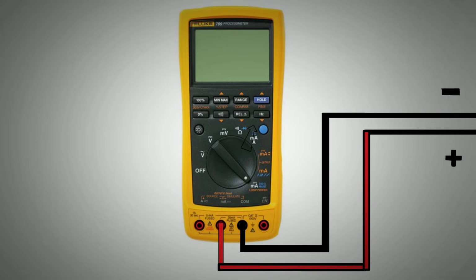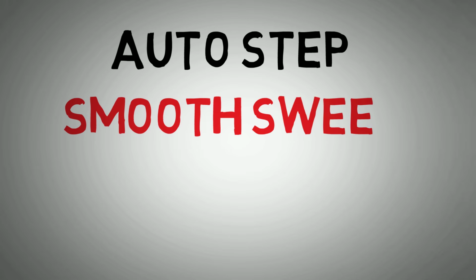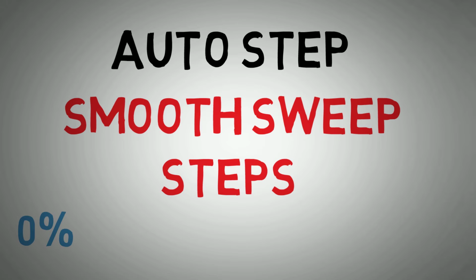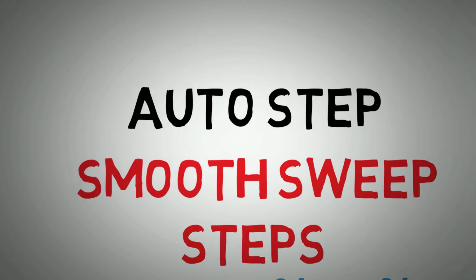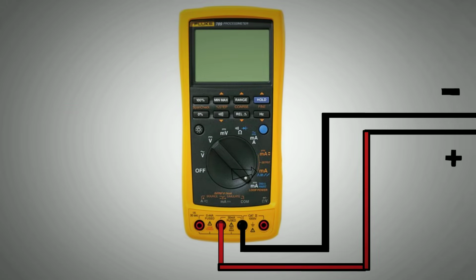It's worth knowing that the Fluke 789 has an auto step functionality that is really useful when lone working on 0 to 20 milliamp or 4 to 20 milliamp loops. This mode will run the meter through the full current range, either in a nice smooth sweep or predetermined steps. Simply connect to your input card the same way as source or sink, but put the meter into the milliamp step mode. Use the blue button to change through the different modes.